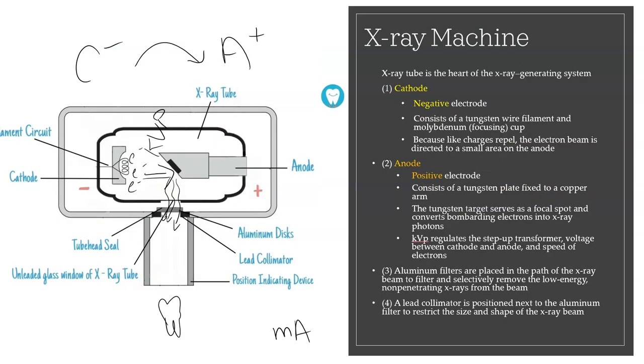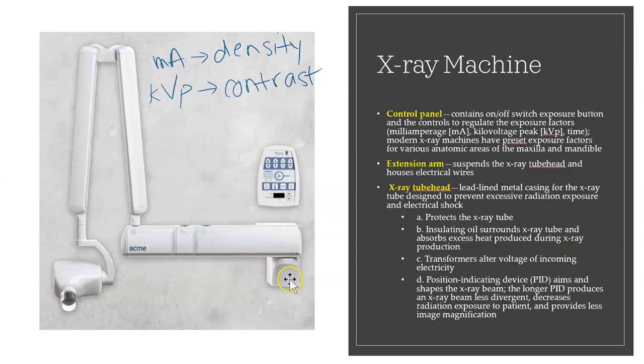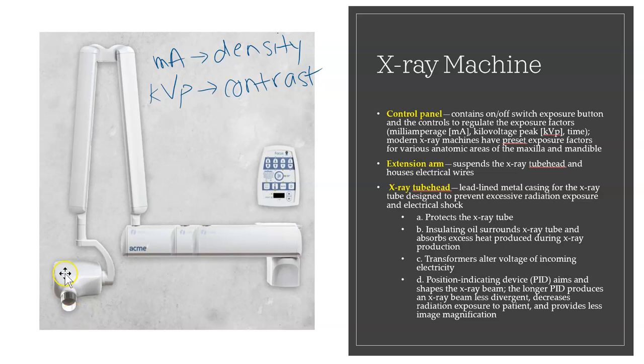In the x-ray machine, there is an extension arm and the tube head, where all the action happens. The PID — position indicating device — is where you aim the beam at the target tooth. A longer PID (like 16 inches) is better because it decreases radiation to the patient and reduces image magnification.